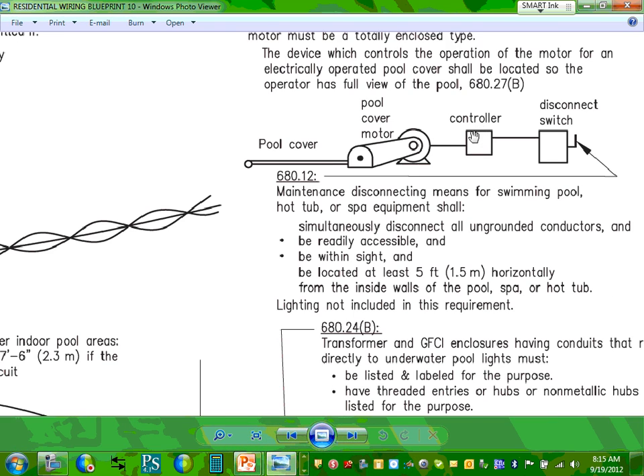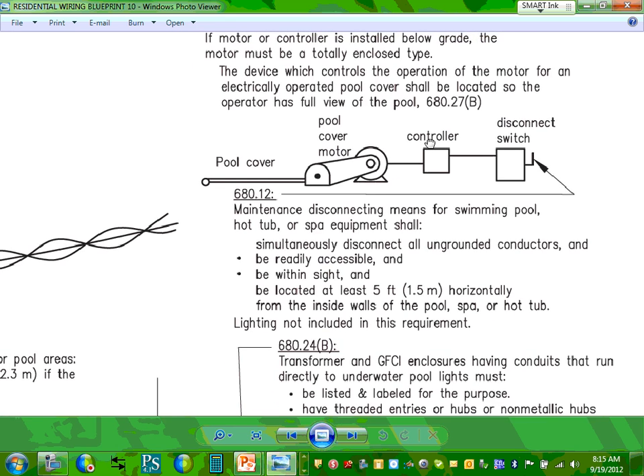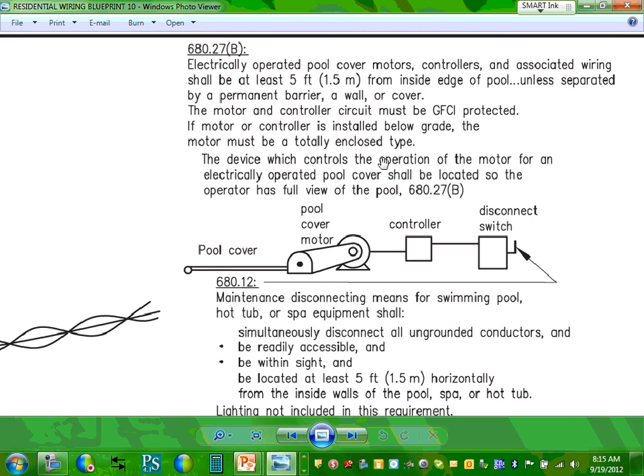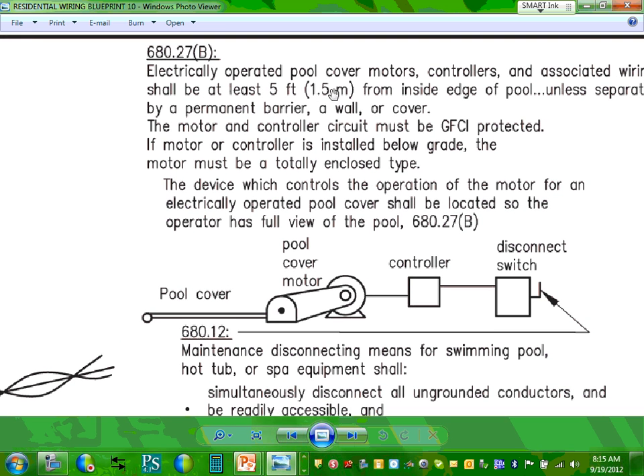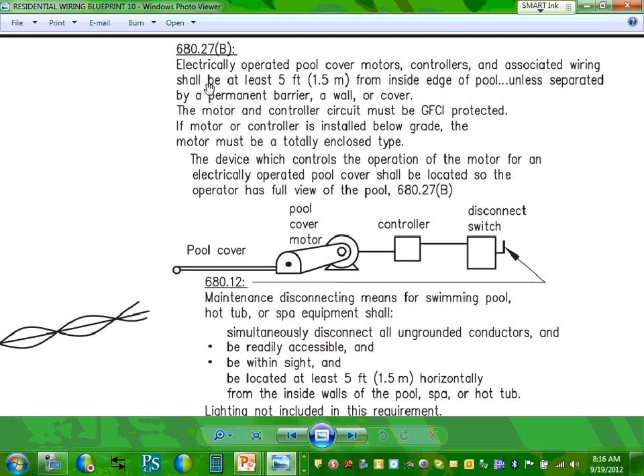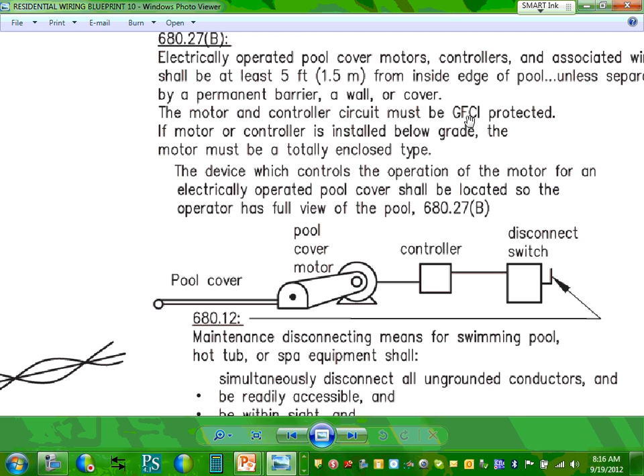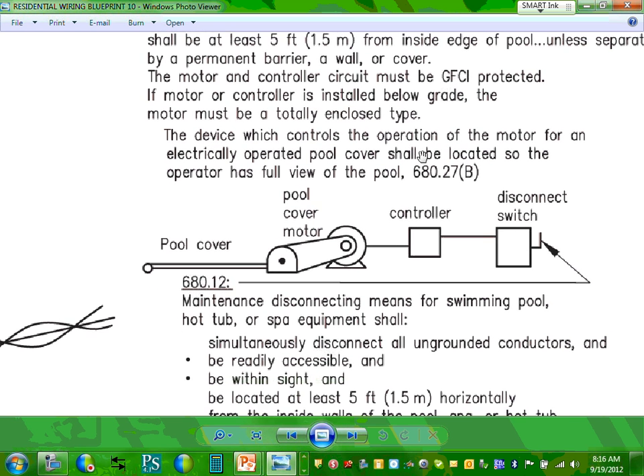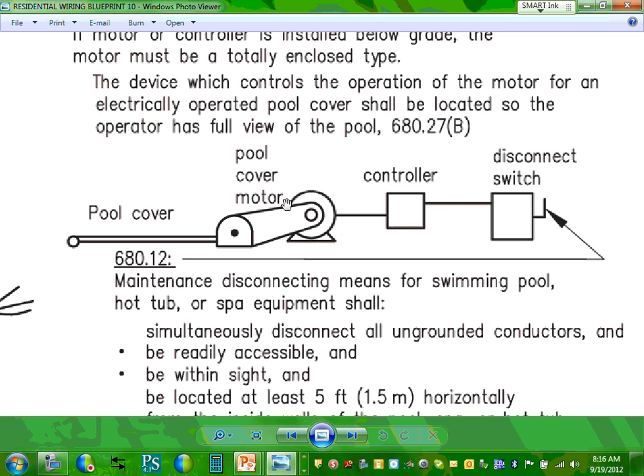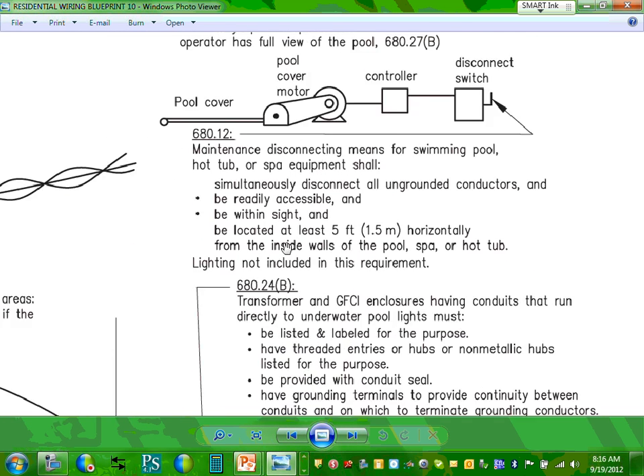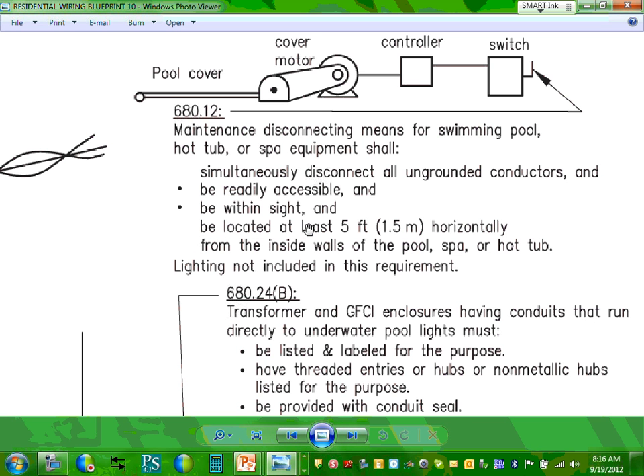A couple of things, guys, about swimming pool here. Maintenance disconnect. Now for the swimming pool, electrically operated pool covers. Your covers, if you have a cover, anybody have seen a cover that covers a swimming pool, electrically operated cover, and all associated shall be at least 5 feet from, you can't bring it closer than 5 feet. They have to be on a GFCI circuit, that motor that runs on it. And you have to have a disconnect. Can you guys see the disconnect, the controller for the cover, and on a GFCI circuit? And not closer than 5 feet. So you can go 5 feet with your disconnect, and that motor that drives the cover has to be on what? GFCI circuit.